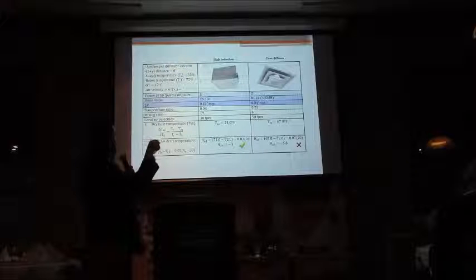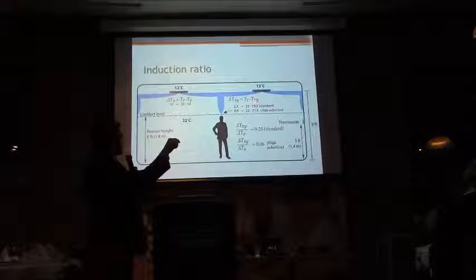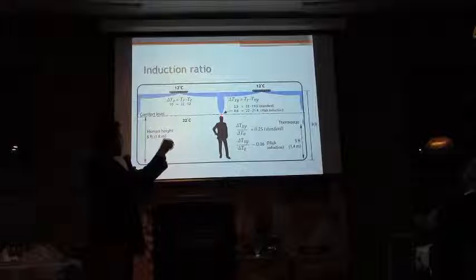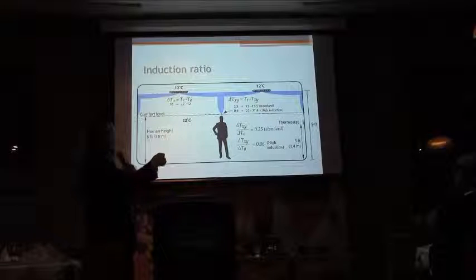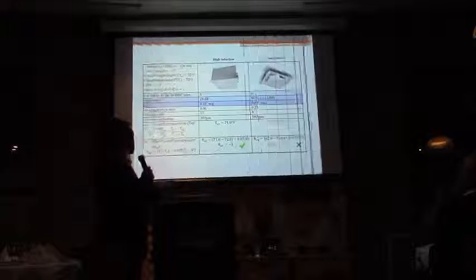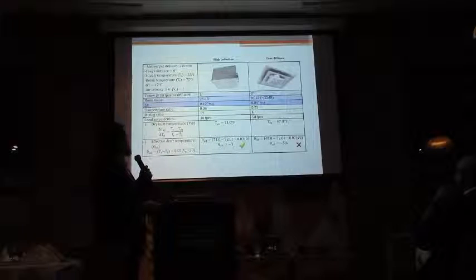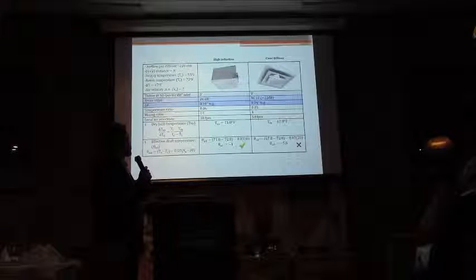So your airflow per diffuser is 220. Your distance, X plus Y, that's X and that's Y. All right, that's what X plus Y distance is. Your supply is 55, your room temperature is 72, so that gives you a temperature difference of 17. And the first thing we want to find is what's the velocity of the air once it reaches the occupied zone.